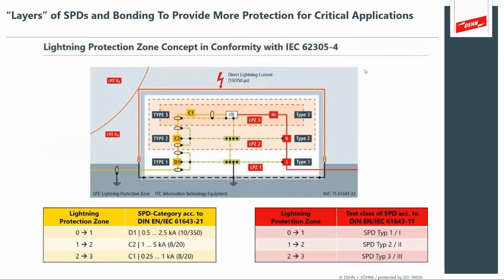And coordination is critical to what's considered the zone concept within IEC 62305-4. And this is what's really nice about a slide like this. This shows you almost all of your aspects. You've got your direct lightning currents that would attach to your air terminals. You have your down conductor systems. You have your earthing systems. But you also want to provide surge protection and additional bonding through the system.